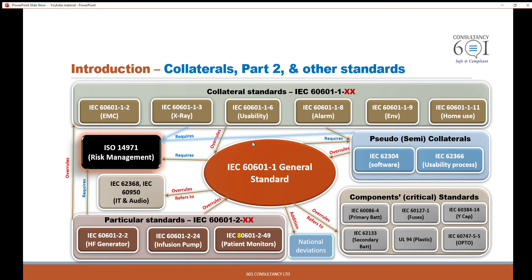Those other standards include collateral standards, and they take the form of IEC 60601-1-XX. They have additional requirements on top of the general standard, but they are based on specific aspects such as home use, environmentally conscious design, alarm systems, and so on. So those are the collateral standards.